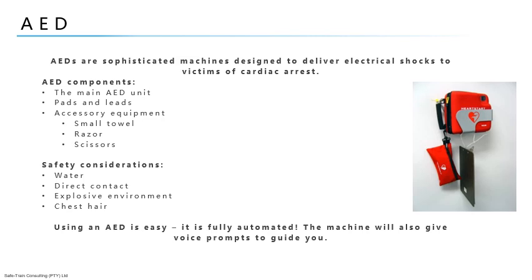Chest hair. The chest pads should be applied to bare skin. Excessive chest hair can disrupt the contact of the pads with the skin and result in burns when the electrical shock is applied. A razor is supplied so you can shave excessive chest hair. Once again, do not spend a long time on this. Shaving cuts or rash is the least of your patient's worries.